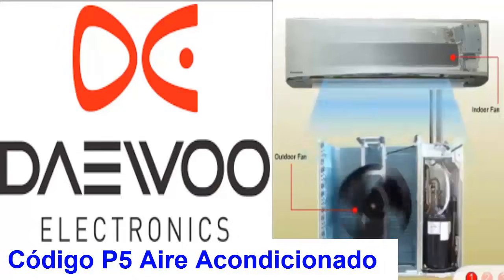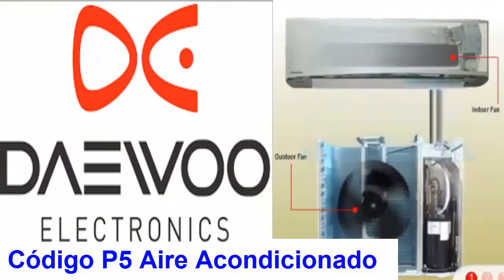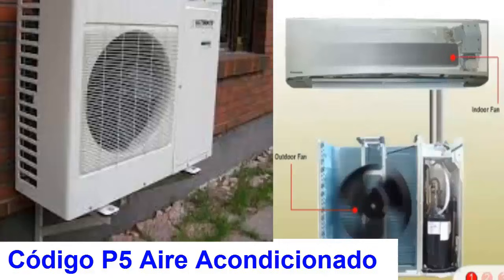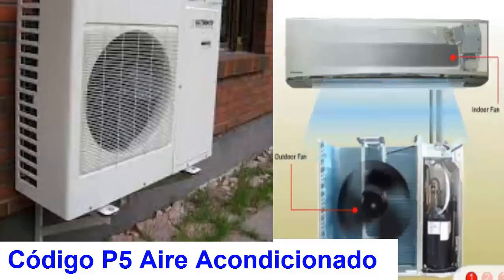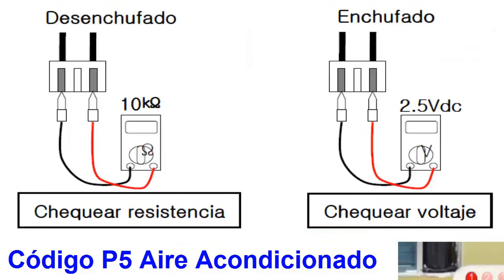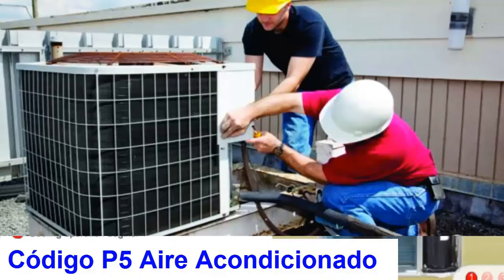5. For Daewoo, the P5 code is related to low outdoor temperature. It is recommended to disconnect the electricity from the equipment for several minutes and check if the problem persists. The outdoor temperature sensor should be checked, ensuring its resistance is neither zero nor infinite. Additionally, the impact of weather conditions on air conditioning operation should be considered, and the settings adjusted as necessary.